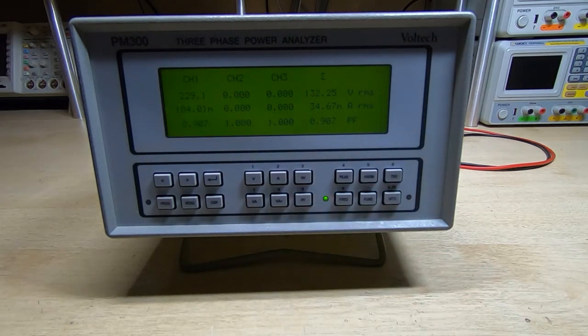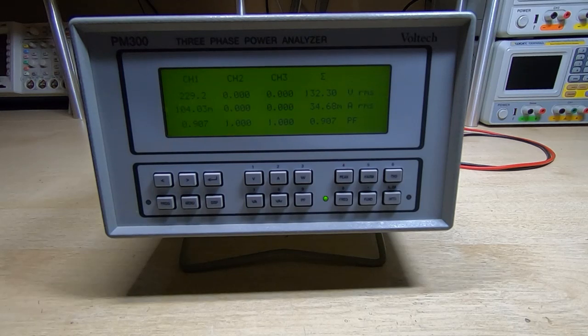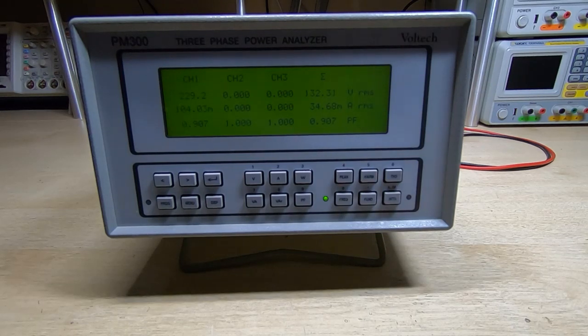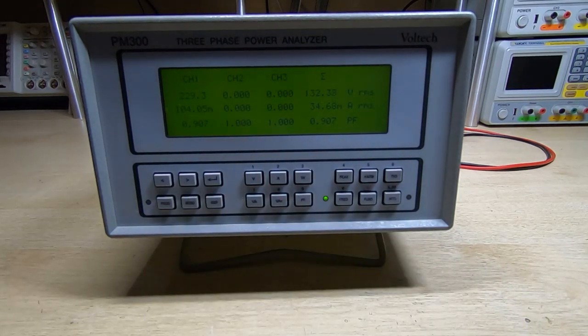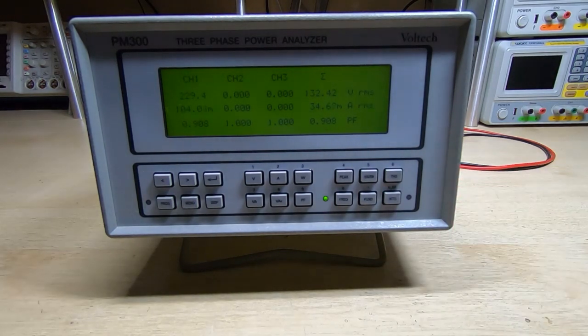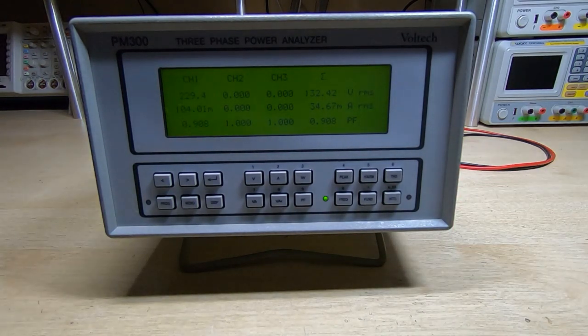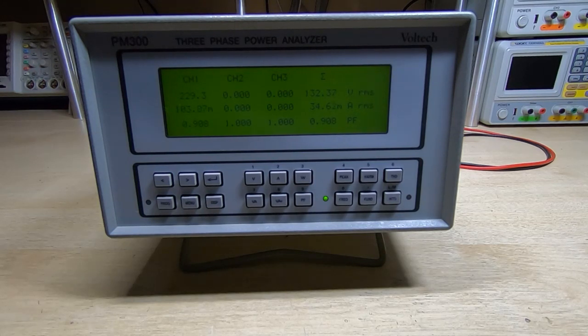And if we now switch to power factor, we'll see if it's reading the same as we were seeing on the PM100, which was just over 0.9. So that's absolutely fine. So yes, we can indeed use the PM300 to monitor itself.